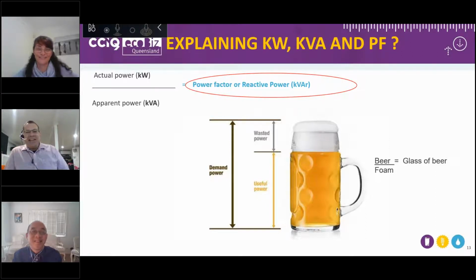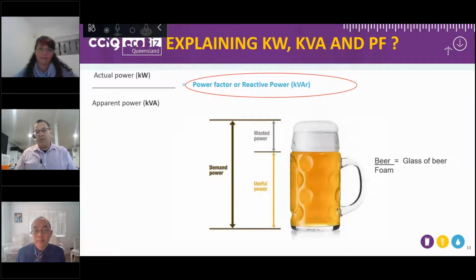So, explaining and understanding power factor. As we spoke about, the formula is kilowatts over kVA equals your power factor. And I like to often use the beer glass example to try and help people understand what it is. So think of the glass as the kVA being delivered. That is the vessel that you can fill and use with power. Now, how you use the power will depend on how much beer you get and how much foam you get to blow off the top of your beer, so to speak.